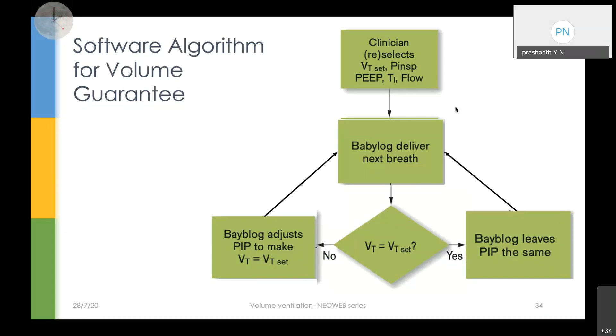Other aspects we also need to look at. This is just an example of how our volume guarantee works. It compares the measured tidal volume to the target volume and automatically regulates the peak inspiratory pressure. We just discussed that. The regulation of PIP is in response to the exhaled tidal volume, so the exhaled tidal volume gives feedback to the next PIP. Depending on the tidal volume, it determines whether it has to decrease or increase the pressure.